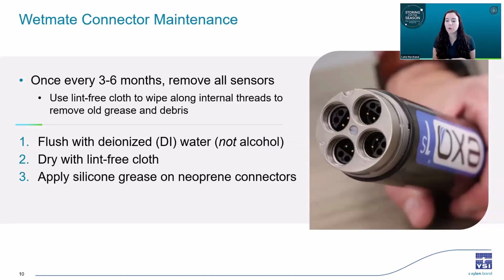So we aren't concerned here about wear and tear from uninstalling sensors, but we are concerned about properly cleaning and lubricating the wet mate connectors. So every 3 to 6 months or so, remove all the sensors, use a lint-free cloth like a Kimwipe to wipe out the ports, get all the dirt and old grease out of the threading. And if there's dirt stuck in the ports, you can flush them with DI water and dry them, but do not flush the wet mate ports with alcohol. That will dry out the wet mate rubber and be very bad for it. If a little moisture is left, that's fine.